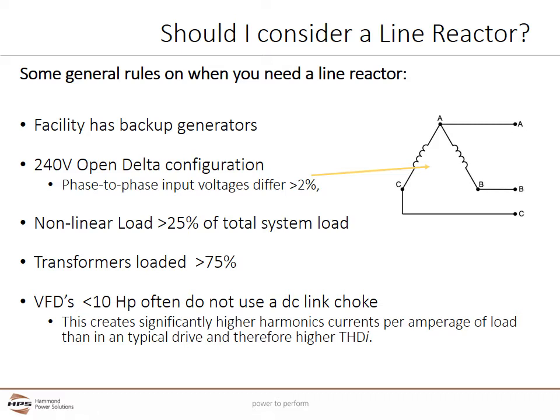If the system's total non-linear load exceeds 25% of the system's total potential load—meaning the actual service entrance rating—line reactors should be considered. For example, with a 200-amp service entrance, if non-linear loads can exceed 25% of 200 amps, always consider line reactors. If a transformer is heavily loaded above 75% for extended periods of time, harmonics can cause dangerous heating, especially with general purpose transformers. Line reactors should be used to reduce harmonics and therefore reduce this extra heating.